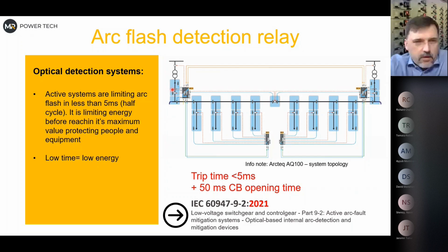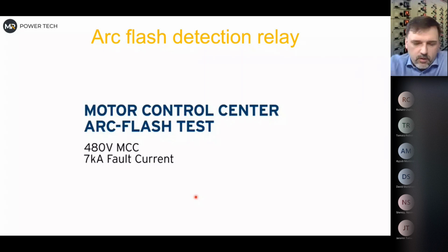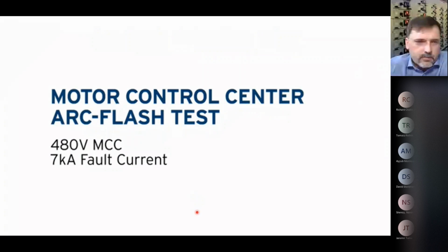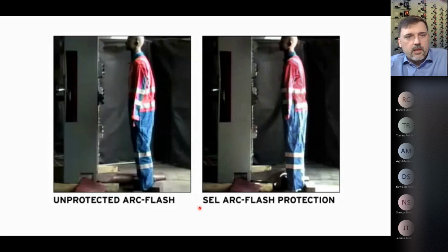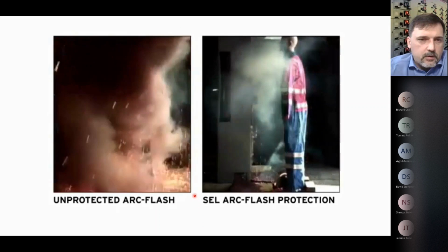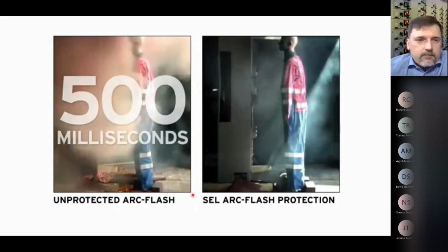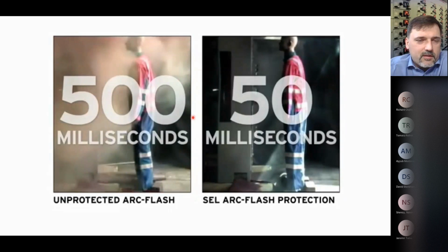From an operation perspective, this is supposed to operate in under 5 milliseconds, typically faster, 3 to 4, and we have to add the breaker tripping time, which might be between 50 and 120 milliseconds if this is a medium voltage breaker, a few cycles. It works this way. I think that's the best explanation. This is the video from Schweitzer lab of their own system. Again, slow motion is the best one.